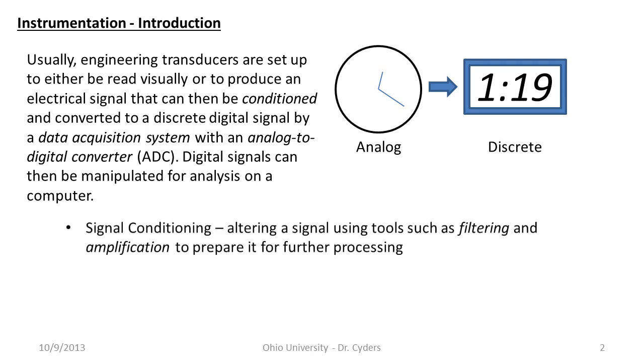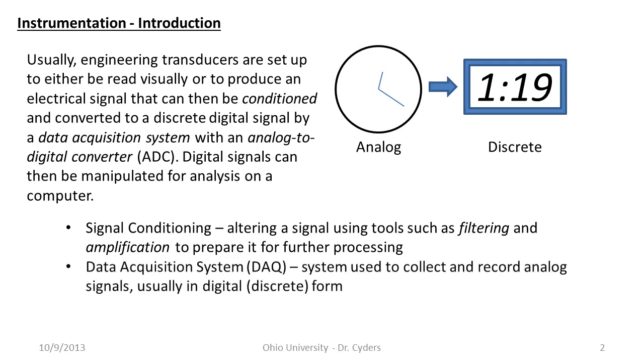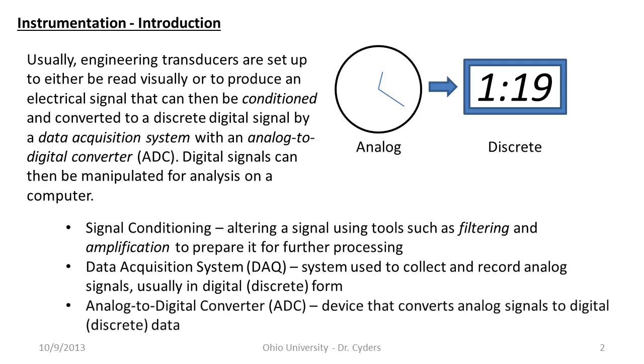To do this, we usually need to condition the signal first. Generally the signal isn't going to look exactly like we want it — we either need to scale it or filter out unwanted frequencies, so we use different signal processing tools to prepare the data for analysis. A data acquisition system, or DAQ, is a system used to collect and record analog signals, usually in digital or discrete form. We convert this continuous analog signal — deciding this much resolution is okay — into computer memory using bits. The analog-to-digital converter is the actual microcircuit device that performs this conversion.